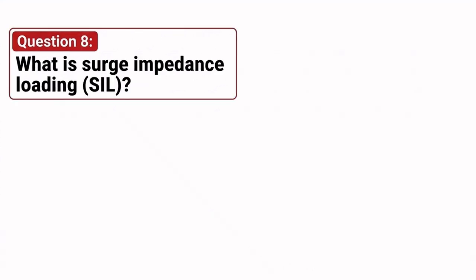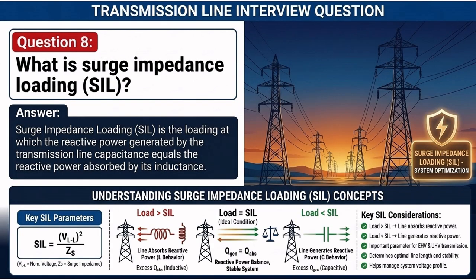What is surge impedance loading, SIL? Surge impedance loading, SIL, is the loading at which the reactive power generated by the transmission line capacitance equals the reactive power absorbed by its inductance. Interpretation: load greater than SIL implies the line absorbs reactive power. Load less than SIL implies the line generates reactive power. SIL is an important parameter in EHV and UHV transmission systems.